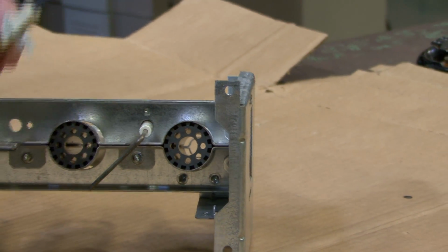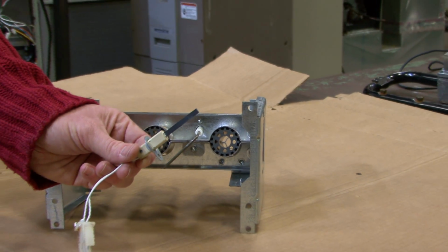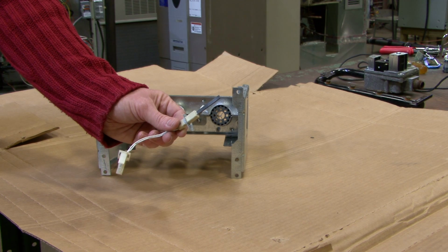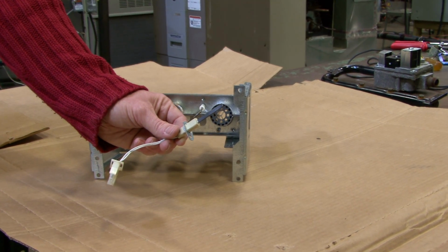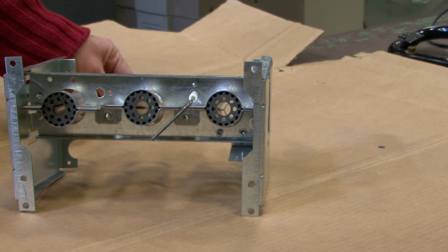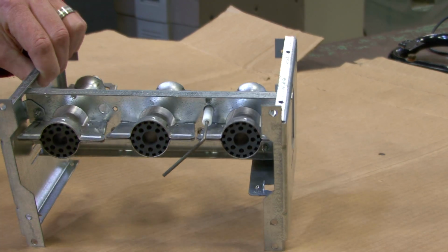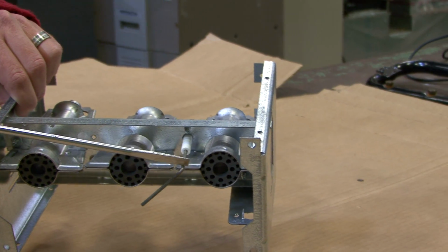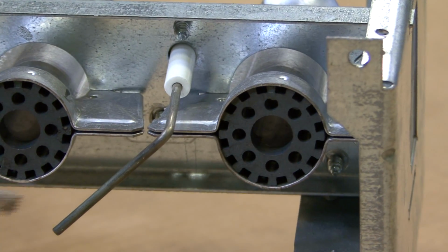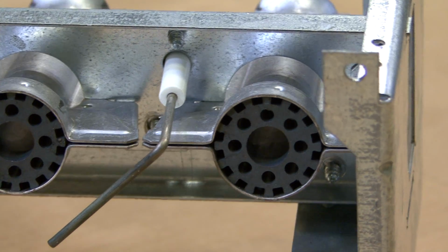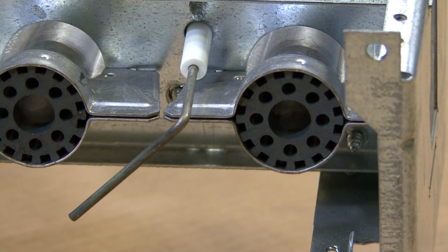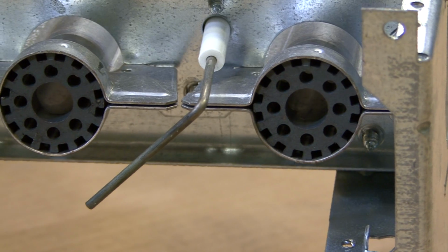Here's an example of our hot surface igniter. Our hot surface igniter comes in a lot of different shapes and sizes. This is one example. This one is made of silicon carbide, and again, you apply electrical power to it and it will glow bright orange and get super hot. Along with that hot surface igniter, our flame proving device is this safety rod right here. This safety rod basically acts like a switch. Whenever the flame is coming out of the burner, it connects a circuit like a switch and turns the switch on. So if there's no flame, the power goes off. If there's flame, the power will stay on.